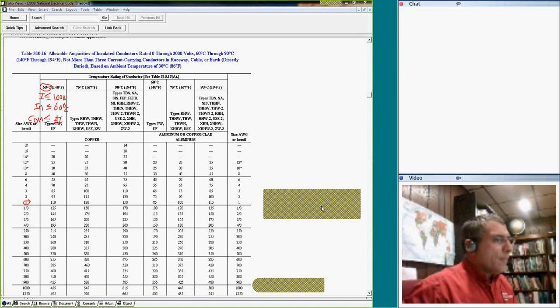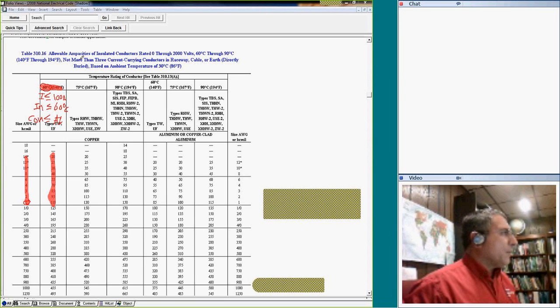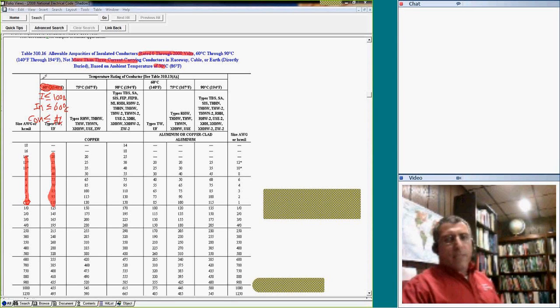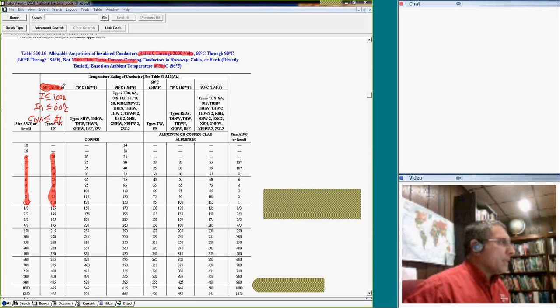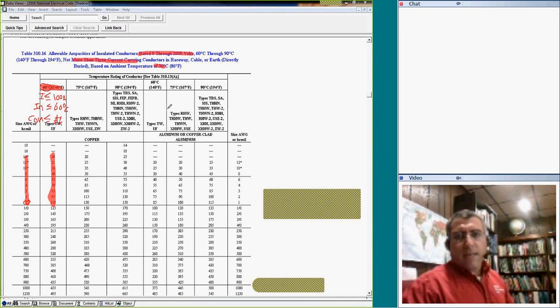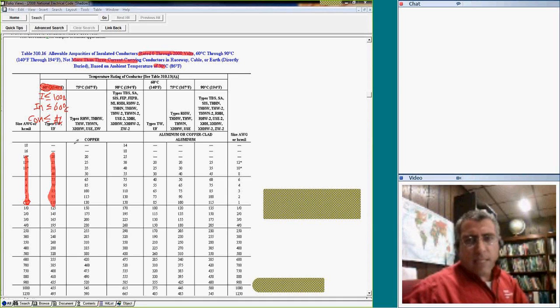So basically these conductors, from here up, go right here with the 60-degree column. I can't emphasize enough, there have to be no more than 3 current-carrying conductors, at a temperature of 30 degrees, and it has to be within the voltage up to this voltage and all this good stuff. All things considered. Any question about how to use the 60-degree column? Any math, any questions?